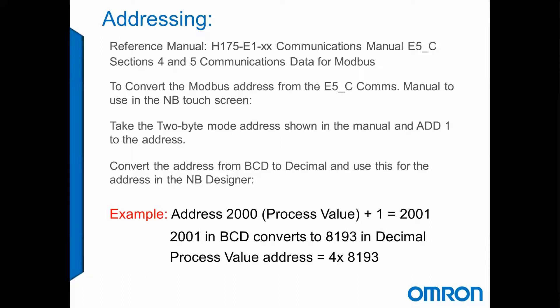As far as addressing is concerned, we're going to use reference manual H175-E1, the communications manual for the E5-C series. Sections 4 and 5 in that manual deal with the communication data for Modbus. To convert the Modbus address from the E5-C COM manual for use with the NB Touchscreen, we're going to use the 2-byte mode address shown in the manual, add 1 to it, convert the address from BCD to decimal, and then use that as the actual address in NB Designer.